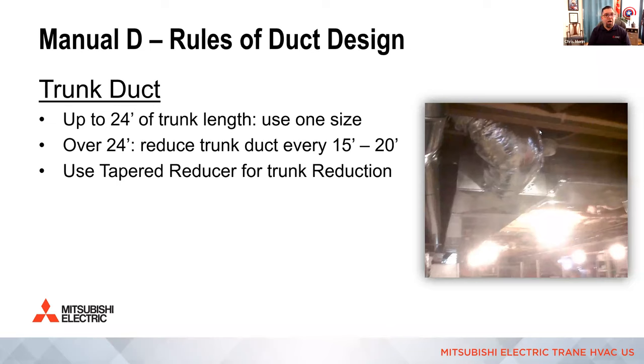So first off, you could run up to 24 feet of trunk and use one size, but typically you have more than just a couple of takeoffs, so you're going to have to downsize that trunk. At the very minimum, if you use more than 24 feet of trunk, you're going to reduce the trunk every 15 to 20 feet. With residential applications, that's actually going to happen more often because you have more takeoffs coming off of one trunk.